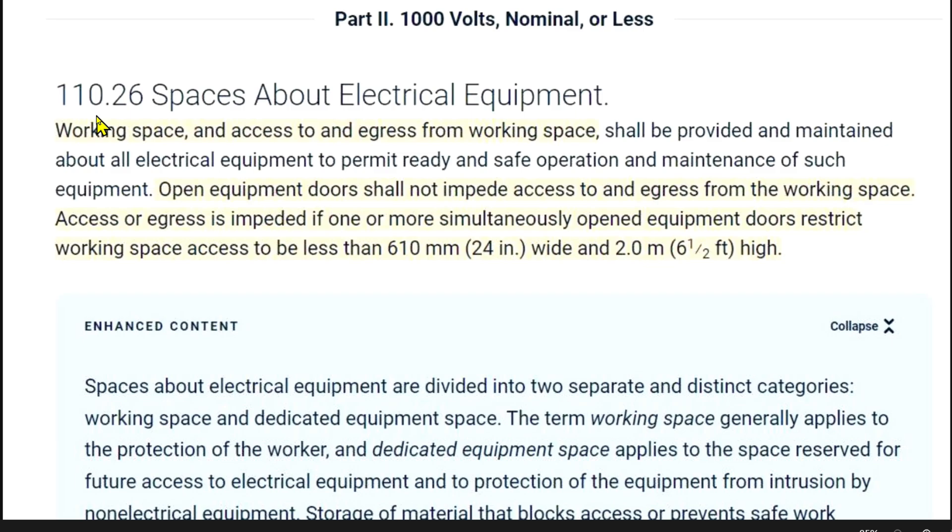Now for the topic of leaving workspace in front of your electrical panels, this is article 110.26, spaces about electrical equipment. Working space and access to and egress from working space shall be provided and maintained about all electrical equipment to permit ready and safe operation and maintenance of such equipment.